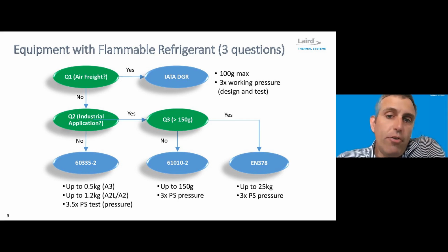If the product is going to go by air freight, the IATA has a requirement that the refrigerant charge in the system be 100 grams or less. And when we think about that, the amount of refrigerant put into a system directly impacts how much the cooling capacity of the system can be. So 100 grams is not a lot of refrigerant. A lot of chillers today that use some of the standard industry refrigerants will have charges of half a kilogram, which is 5 times what we're talking about here. And those are only cooling about 5 kilowatts. So with 100 grams, there's a real need to have some design expertise in order to maximize the cooling performance of the system while still keeping that refrigerant charge down. And so we'll talk a little bit more about some of the technologies that we use in our systems in order to improve that.